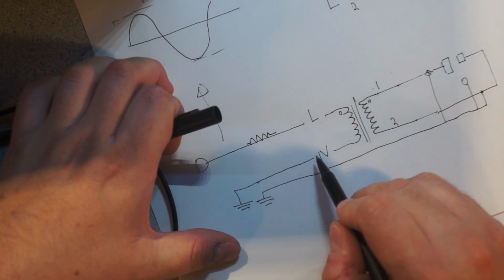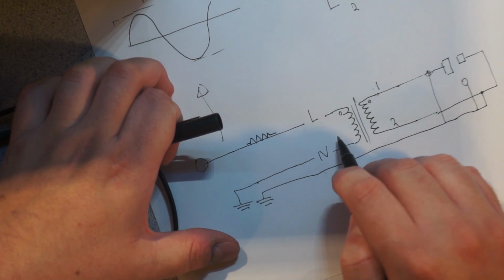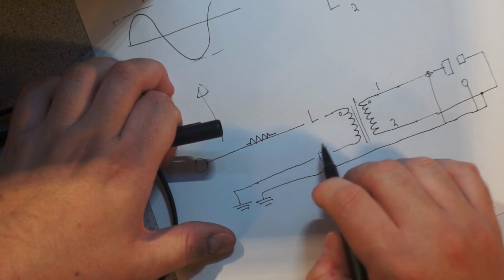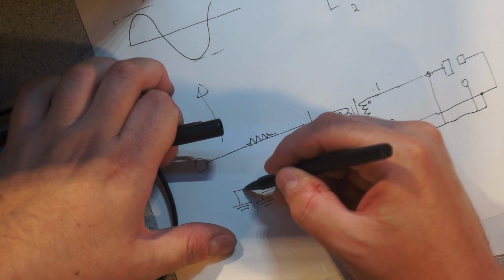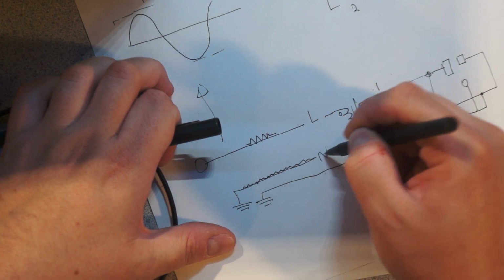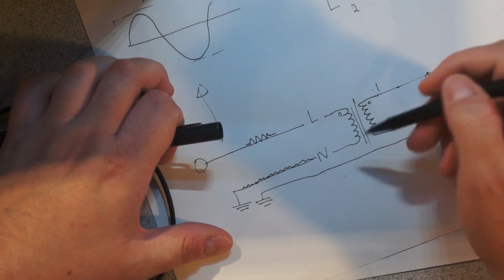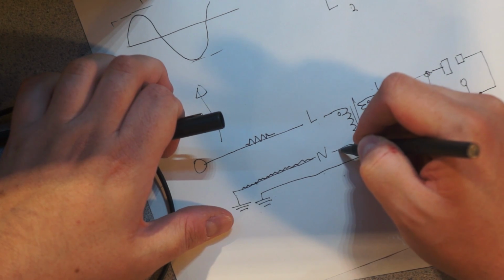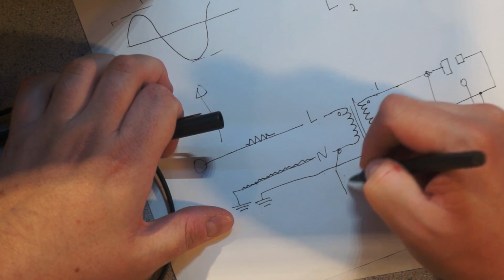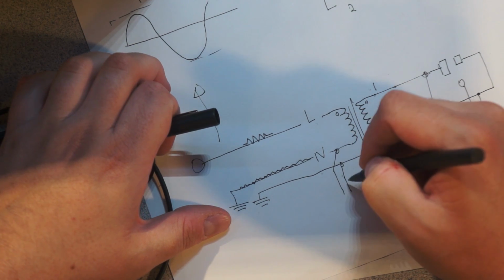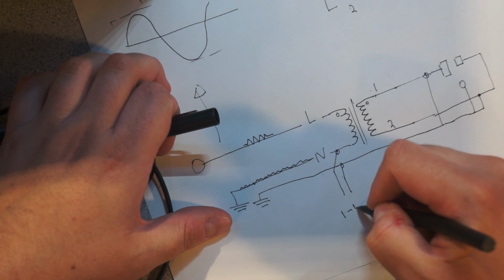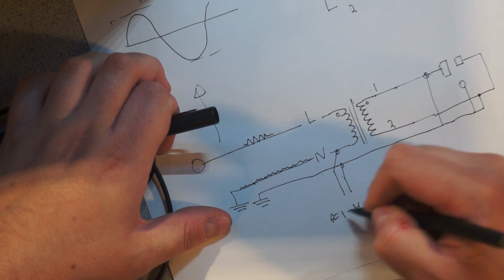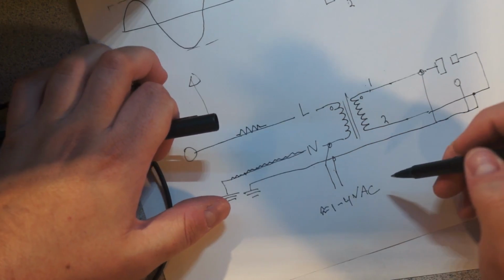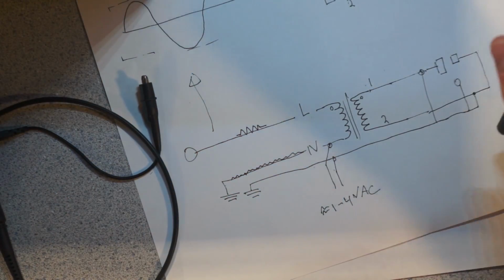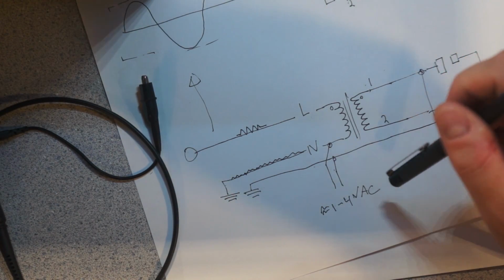The other problem is that there is resistance in your neutral. You've got these long wires, maybe 30, 50, 100 feet running back to your breaker, which is basically a whole lot of little resistors, basically one long resistor. It's going to be small, but it's very common, if you measure the voltage between your neutral and your ground, to have 1 to 4 volts. In my house it's about 3, which is indicative of not the highest quality, but what do you expect from a house made in the 60s?